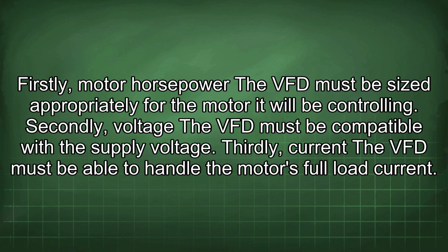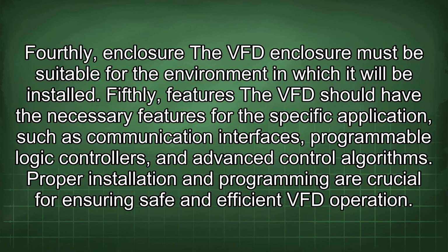Secondly, voltage. The VFD must be compatible with the supply voltage. Thirdly, current. The VFD must be able to handle the motor's full load current. Fourthly, enclosure. The VFD enclosure must be suitable for the environment in which it will be installed. Fifthly, features.